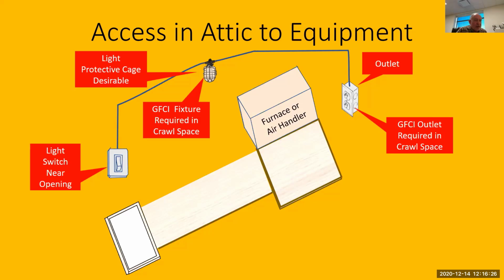There's been a requirement for many years that you have to have a receptacle outlet within 25 feet of the unit for servicing, whether it be an AC unit on the outside, condenser, furnace, air handler, or whatever. You have to have a receptacle. The 2017 code changed that so that the receptacle and the light under the house in a crawl space area has to be GFCI protected. That came about in the 17 code.